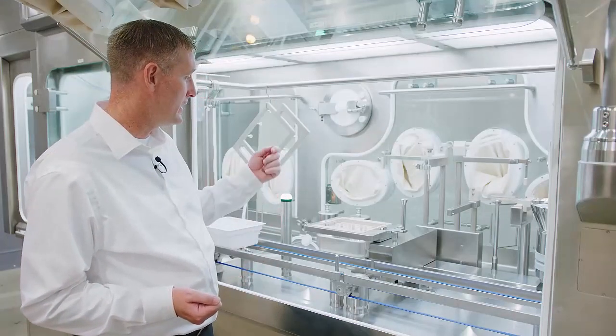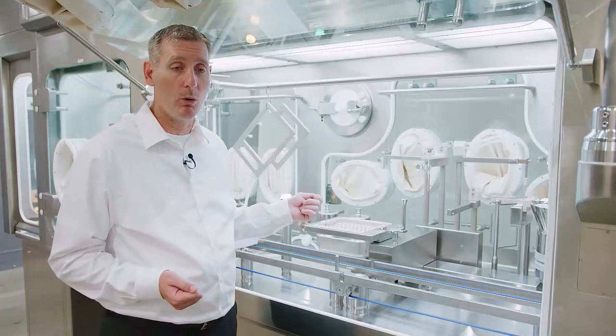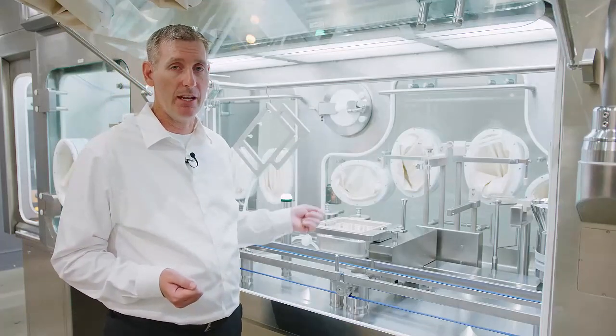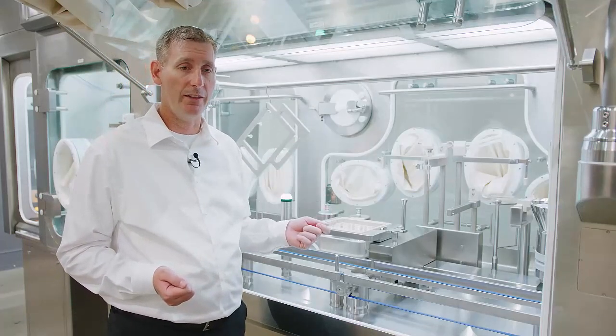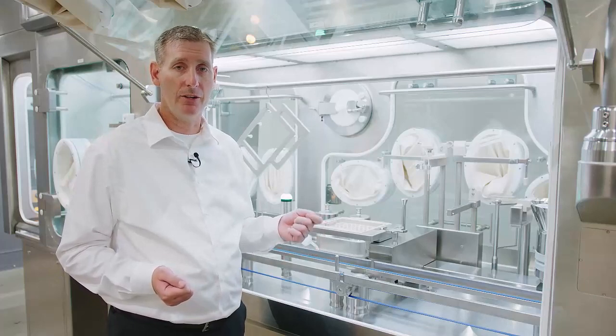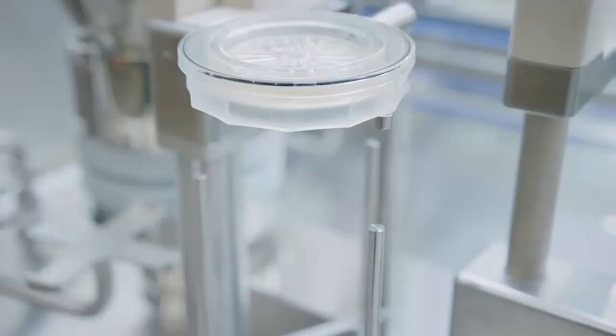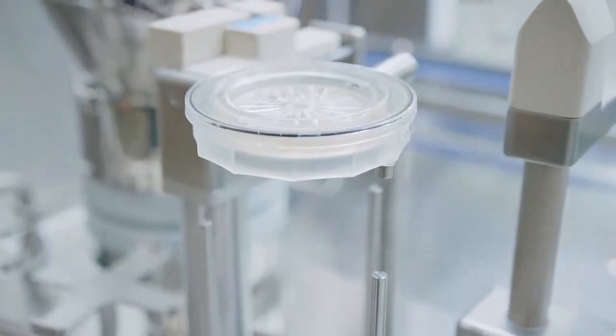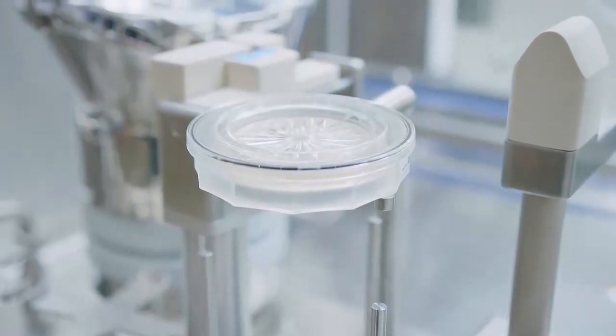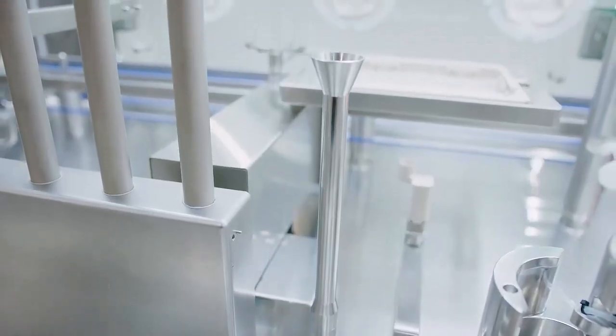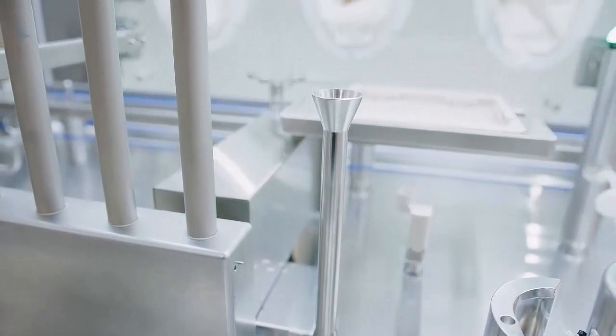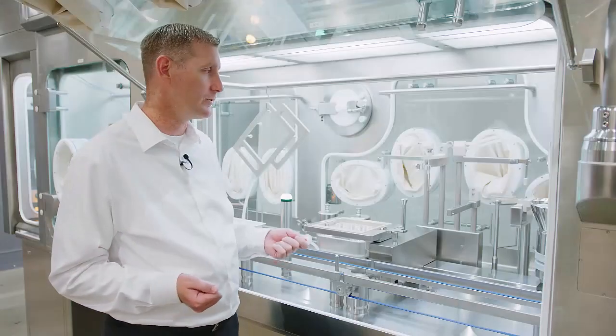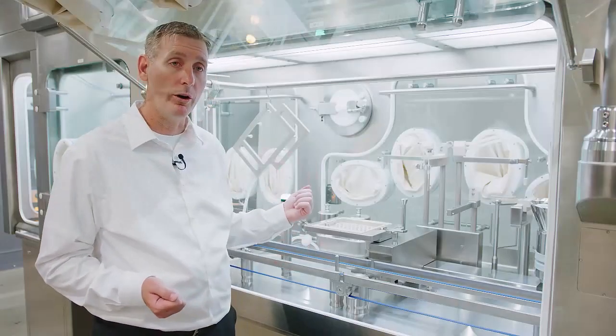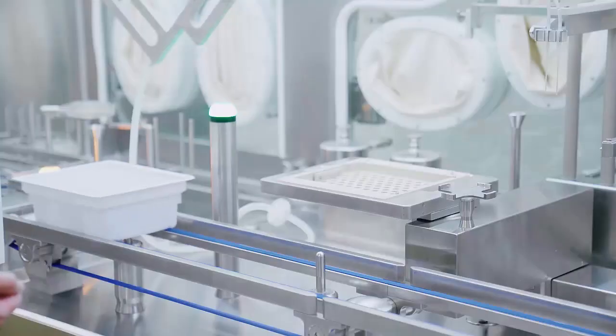And then the necessary and very important instrumentation to ensure that the environment is under proper control. Those would be the viable active air sampling position plates, and the non-viable particle sensors that are continuously monitoring the amount of particulate within the aseptic core for proper processing.